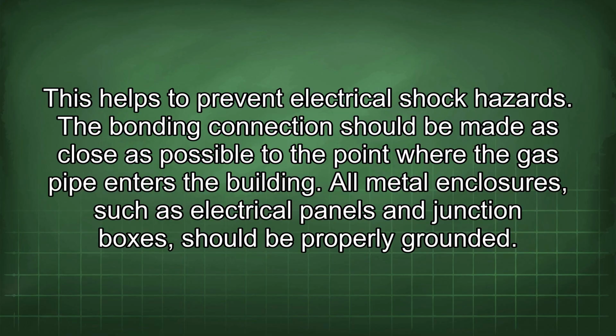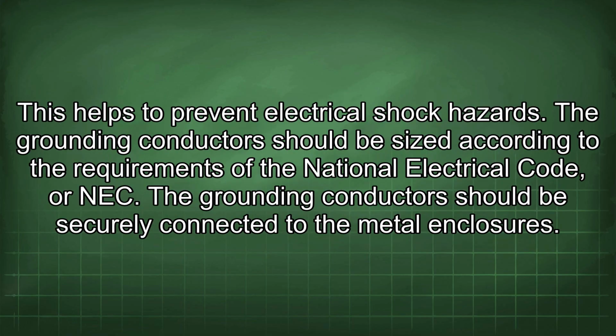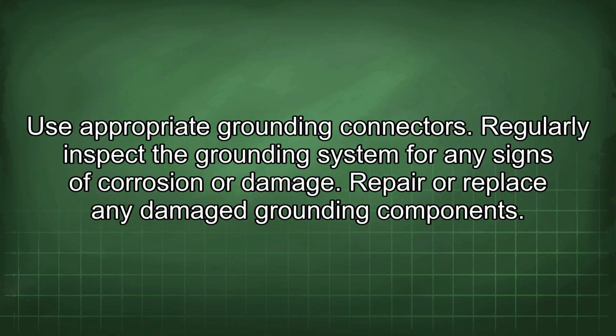All metal enclosures, such as electrical panels and junction boxes, should be properly grounded. This helps to prevent electrical shock hazards. The grounding conductors should be sized according to the requirements of the National Electrical Code, or NEC. The grounding conductors should be securely connected to the metal enclosures. Use appropriate grounding connectors. Regularly inspect the grounding system for any signs of corrosion or damage. Repair or replace any damaged grounding components.